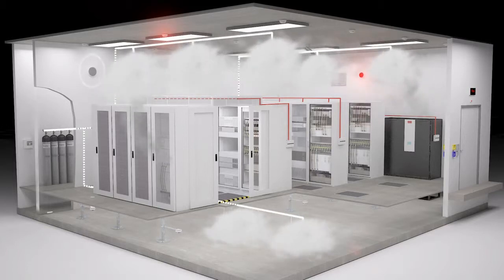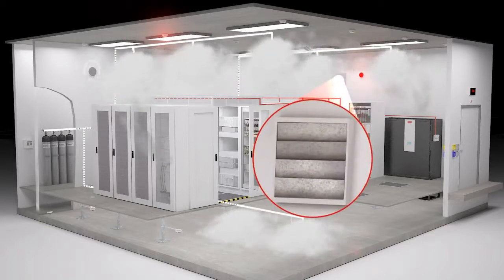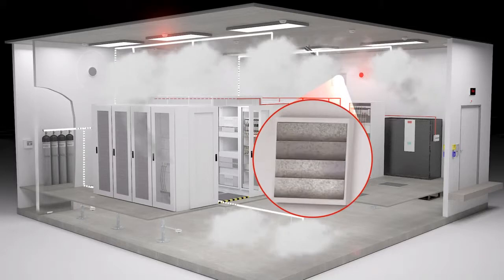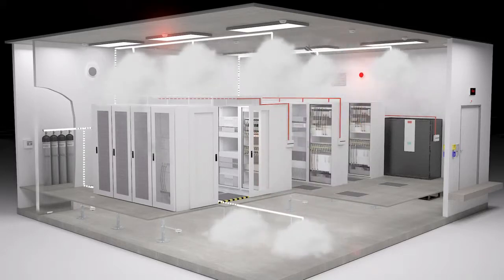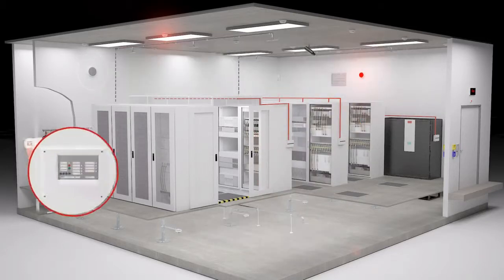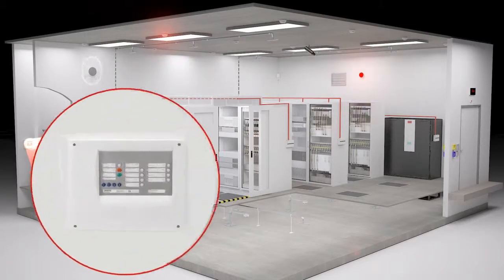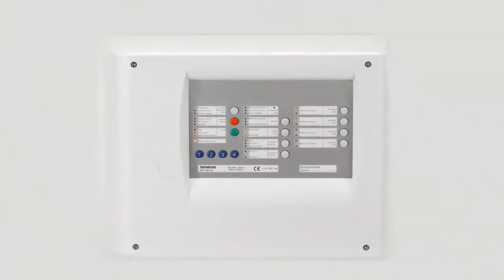As the flooding begins, the overpressure flaps open to ensure the structural integrity of the room. After discharging the entire extinguishing agent, the retention time of 10 minutes begins in order to prevent re-ignition.